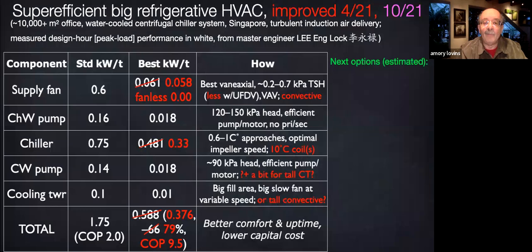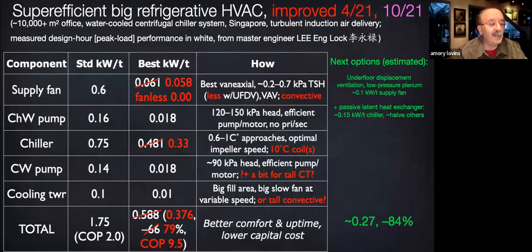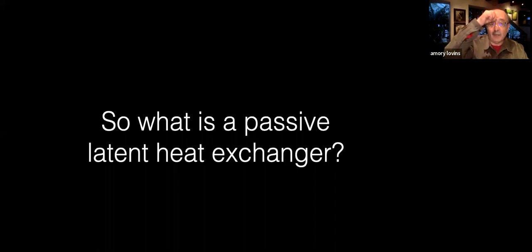Okay, well, what's next? First, about half the remaining cooling system power could be saved by underfloor displacement ventilation, as we saw earlier, plus a passive latent heat exchanger. What's that? Well, dry climate buildings like RMI's Innovation Center in Colorado use a heat exchanger to recover 93% of the sensible heat, and therefore they preheat, or perhaps in the summer pre-cool, the outside air coming in from the exhaust air going out. But if you're air conditioning a big building that needs the humid outside air to be dehumidified as it enters, isn't it wasteful to discharge stale but still relatively dry air from the building and waste its dryness, its lack of latent heat?